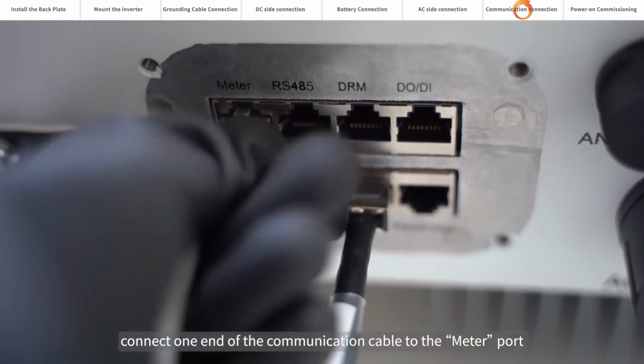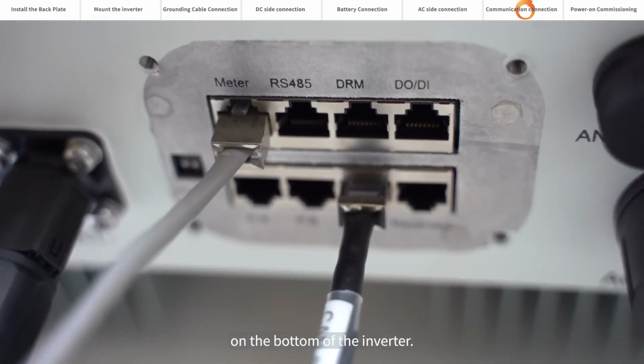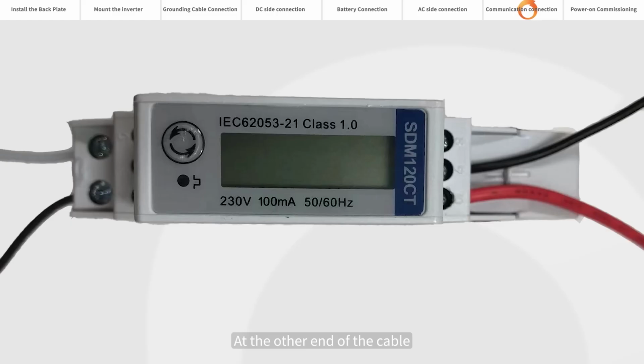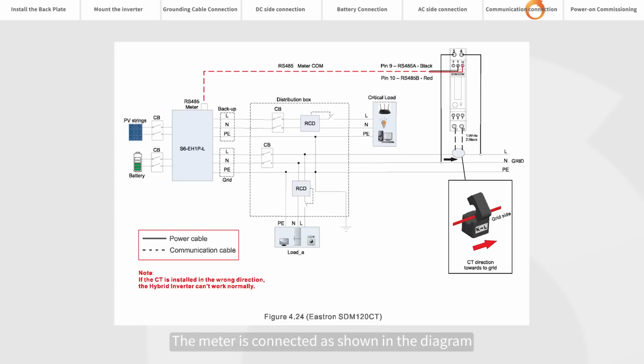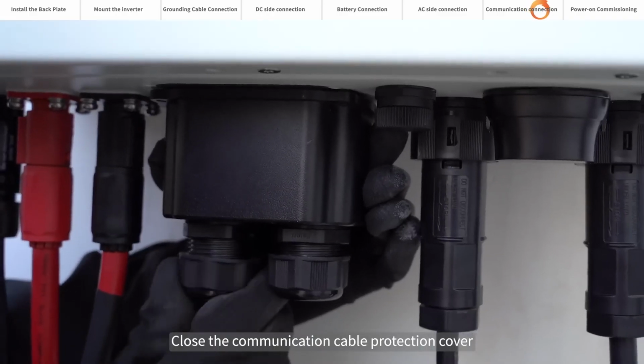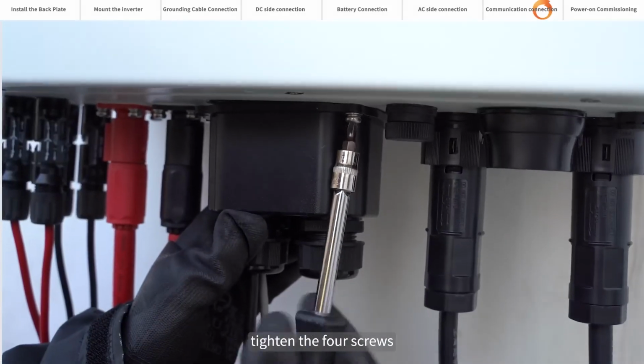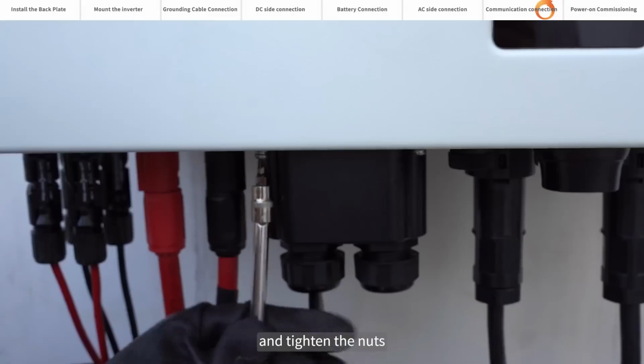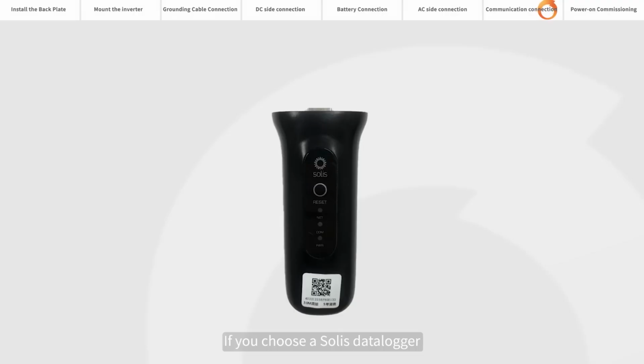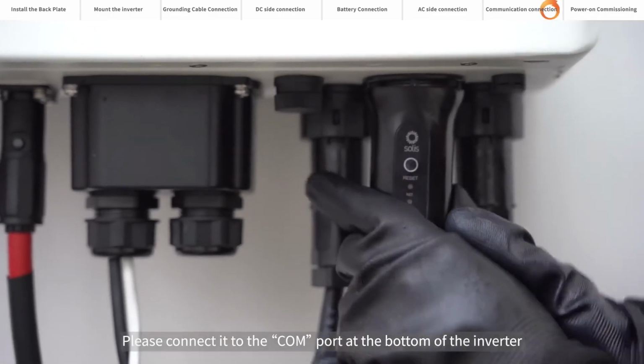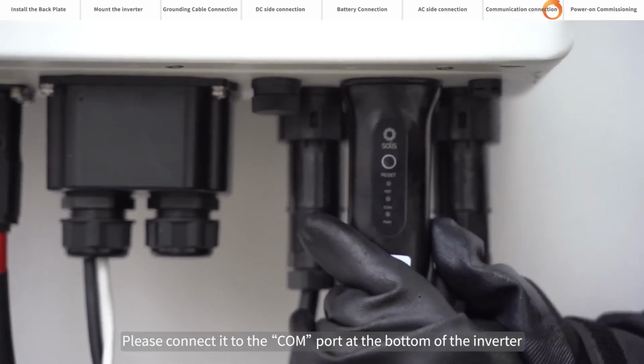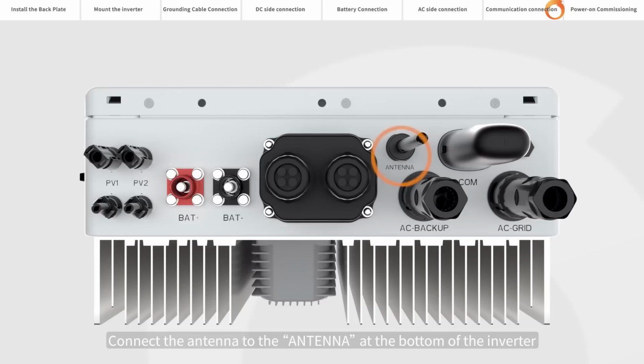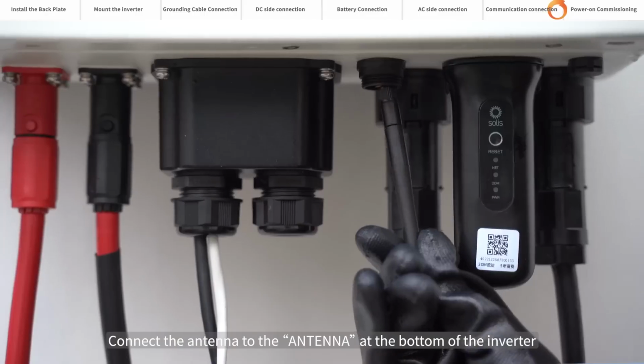Connect one end of the communication cable to the meter port on the bottom of the inverter. At the other end of the cable, the black line is connected to pin 9, and the red line is connected to pin 10. The meter is connected as shown in the diagram. Close the communication cable protection cover. Tighten the 4 screws, and tighten the nuts. If you choose a Solis data logger, please connect it to the COM port at the bottom of the inverter. Connect the antenna to the antenna port at the bottom of the inverter.